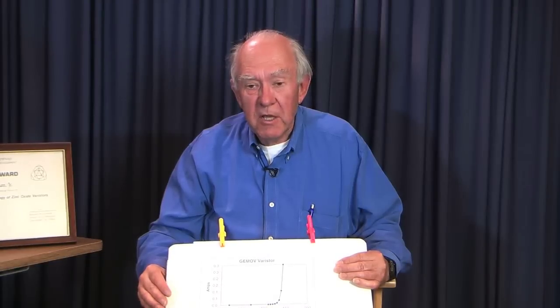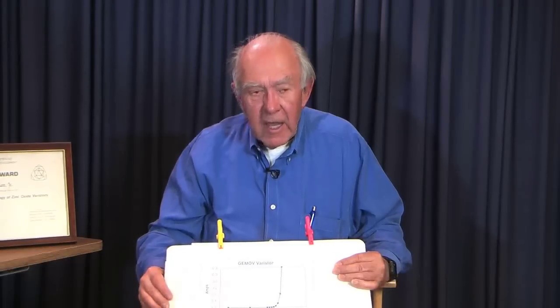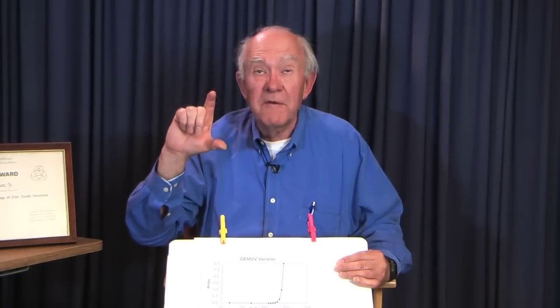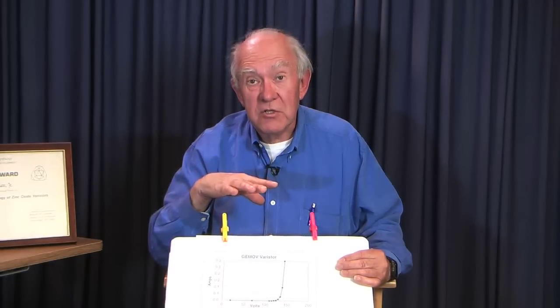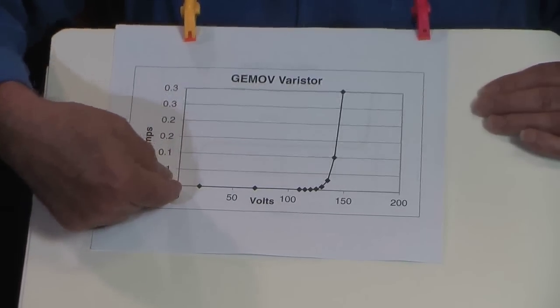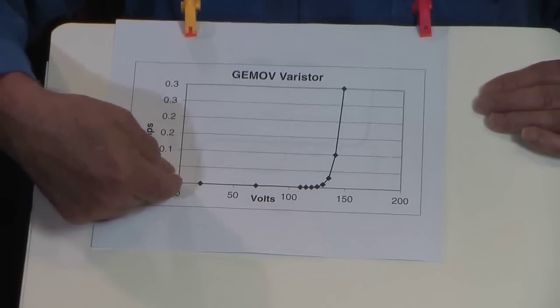The purpose of the varistors — metal oxide varistors, and the GE brand of these was the GEMOV — is their ability to clamp voltages. They basically sit on a circuit and do nothing at all until the voltage starts to rise above an acceptable level, and then it clamps the voltage at that point so that you don't damage the other circuits and components on the circuit. Here we see as we raise the voltage it draws almost no current — it looks inert, almost like it wasn't in the circuit at all.